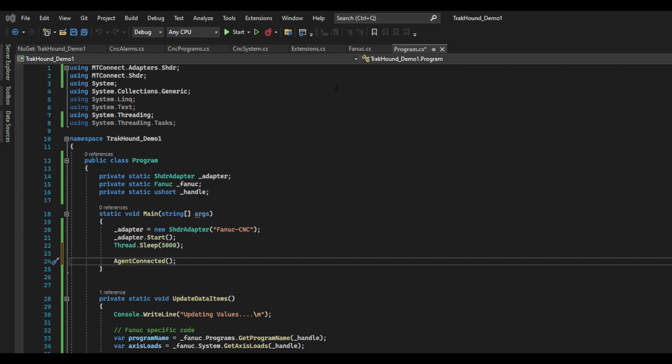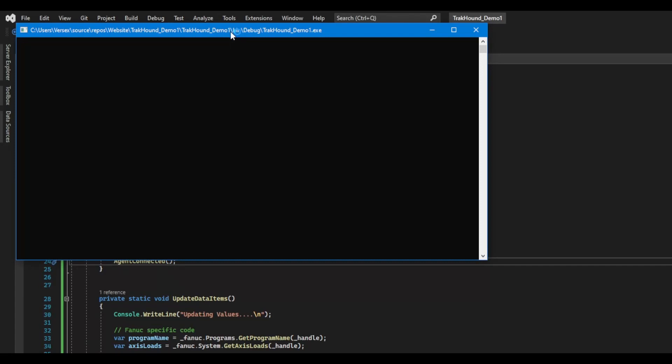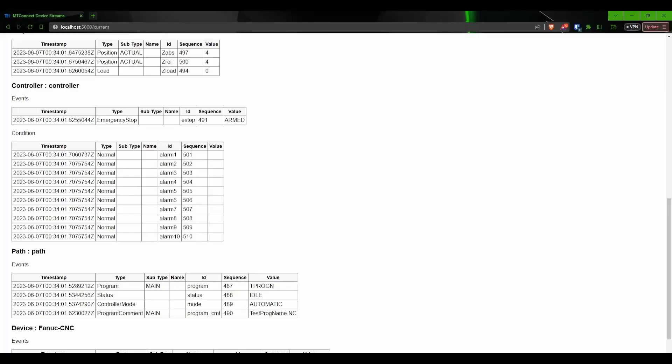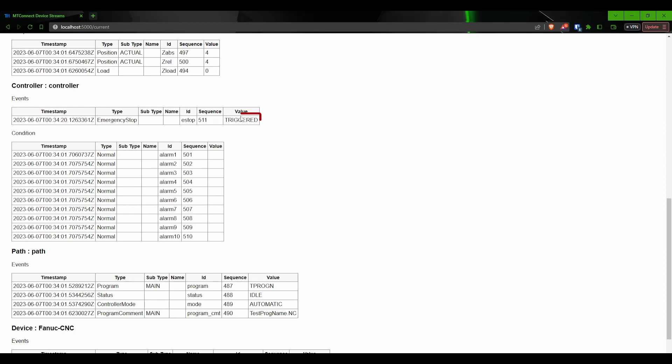Now we can run our adapter. When we run this, it is going to start a connection to the agent. Every time we read information from the machine, it is going to take the information that has changed since the last time it was sent and convert it into the SHDR format that we saw earlier. The data points will then be sent to the agent on port 7878, where it will undergo another conversion to XML format and finally be sent over the network for any MTConnect client to read.